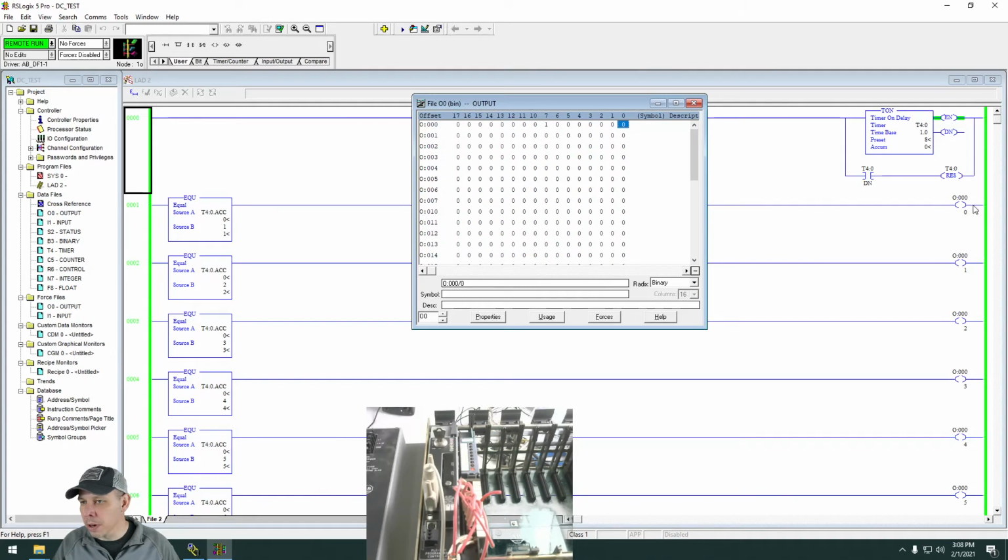So the top is the card location, and that's the individual bit location, 1, 2, 3. And you see these 1, 2, 3 going through here, and that goes 0 through 7 on the output lights. So whatever device I had connected with these, I wouldn't put red wires on this because it's DC. I would put blue wires. That's the general way people do things. Red is usually for 120 volt AC, and blue is usually for 24 volt DC.